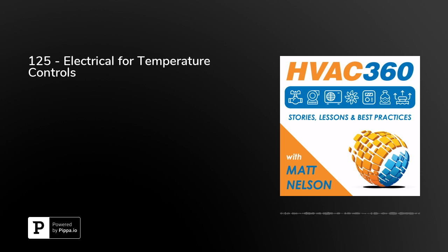Now, what do I mean by that? Because we use the 4 to 20 milliamp rather than a 0 to 20 milliamp, when we're feeding it power at 4 milliamps, that equates to 0 in a device. So if we don't get 4 milliamps, and we're getting 0 milliamps, we know that there's something wrong with the system.